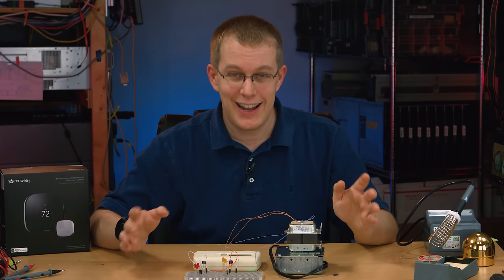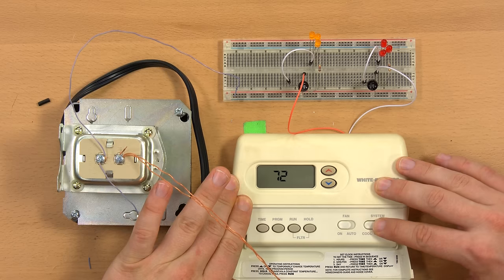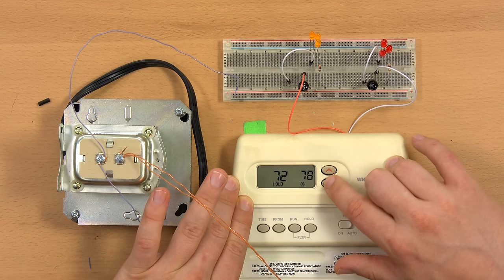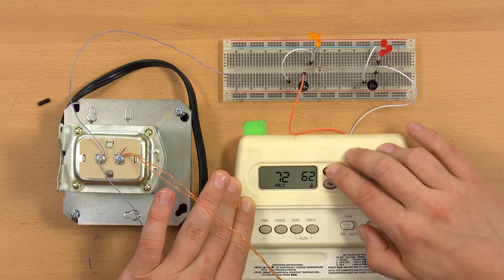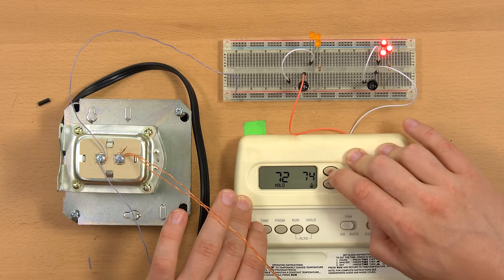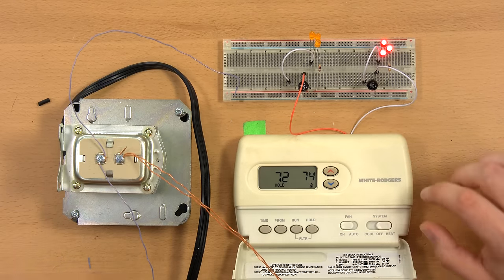The wiring looks really complicated but it's not. I'll turn this on — the thermostat comes on. If I set it to cool, the set point is 78 by default; if I bring this down below 72 it's going to want to turn the cooling system on — and the cooling system comes on. If I change it over to heat mode it defaults to 62; the thermometer reads 72, so if I turn it above 72 the heating system should come on — and it does. This thing's working like it should, which it wasn't when it was on my wall, which is weird.